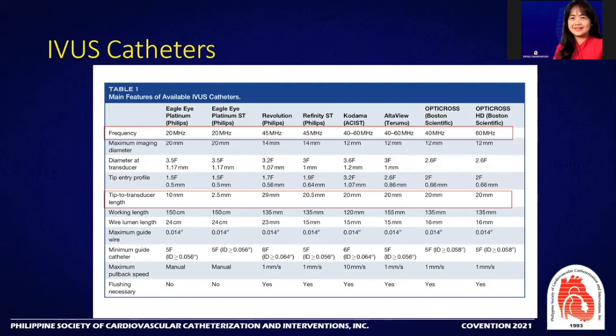Now, another significant difference here is the distance of the transducer from the tip, from 2.5 millimeters to as far as 29 millimeters. So in cases where you want to evaluate the CTO plaque closest to the tip, it is advisable to use the catheter with the shortest distance.